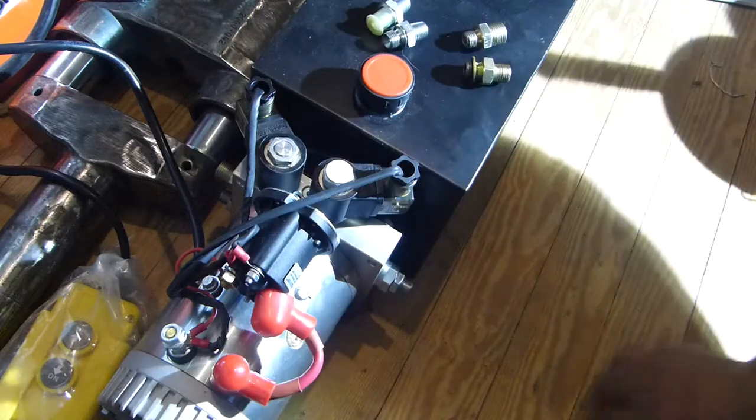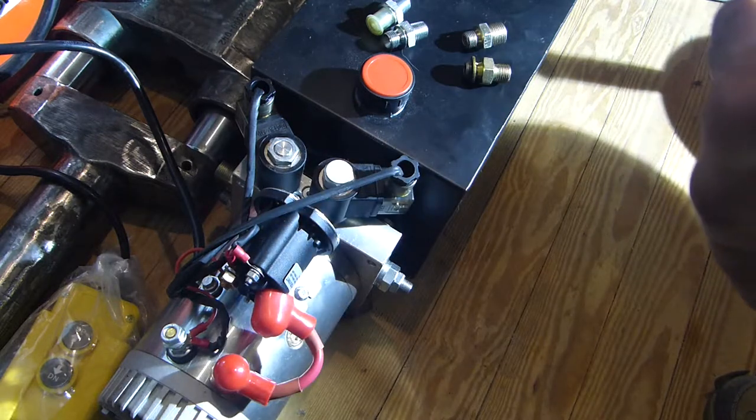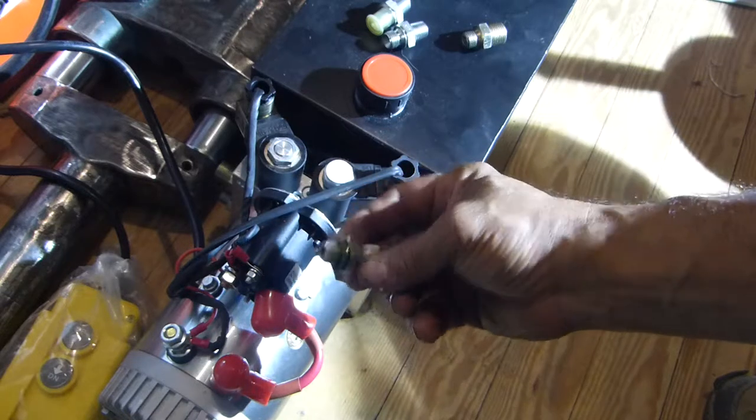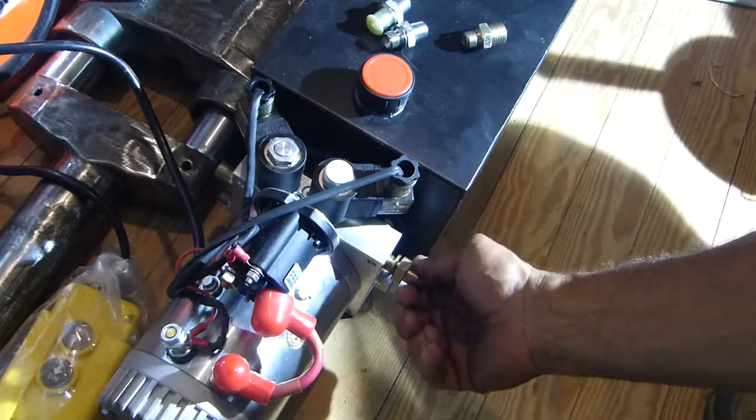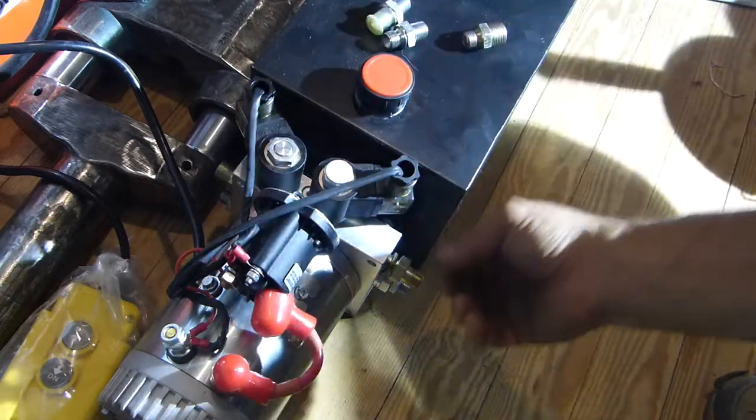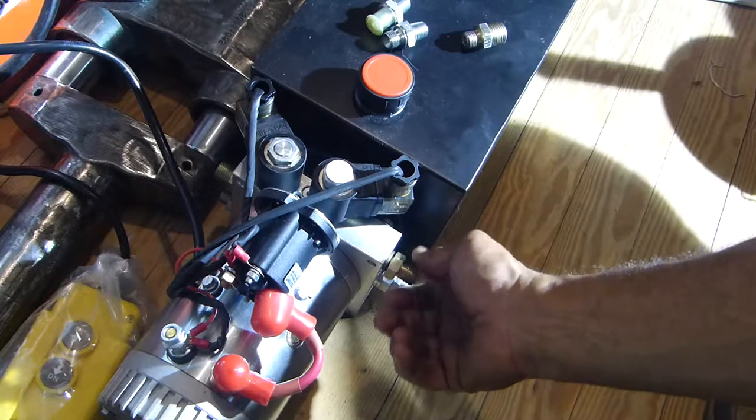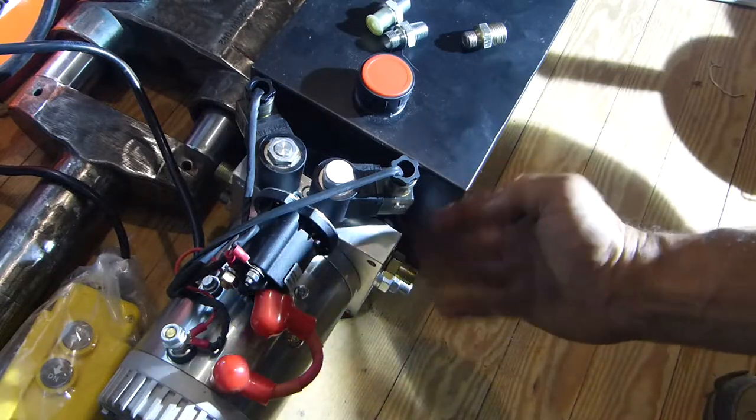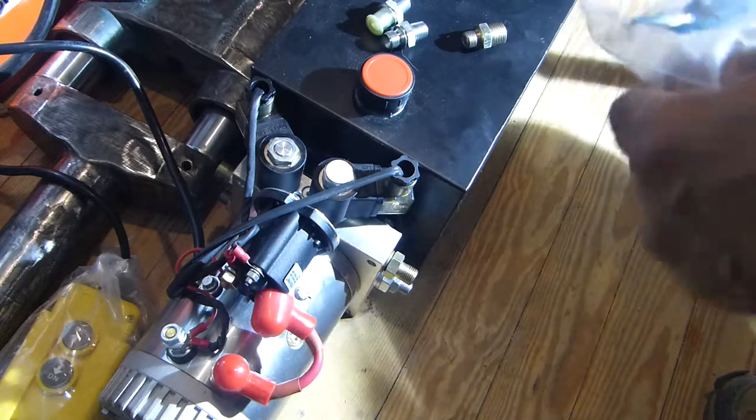Or it took long enough - and this is what it came with. It took long enough but I think we can just simply go with, let me look at my notes here, BSP. You're just going to use a quarter inch BSP male fitting. So you would google and search anything says quarter inch BSP to whatever fitting you want. If you want JIC, if you want NPT national pipe thread, you would just look for that connection and you're going to get it done for cheap - maybe eight dollars to eleven dollars per fitting.